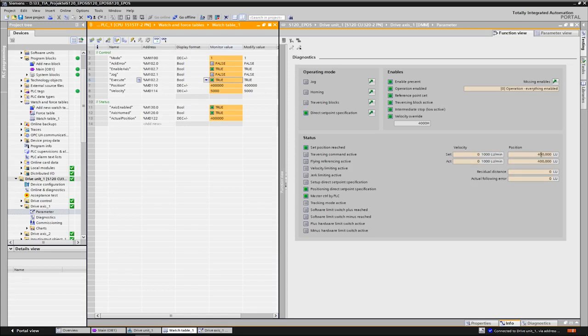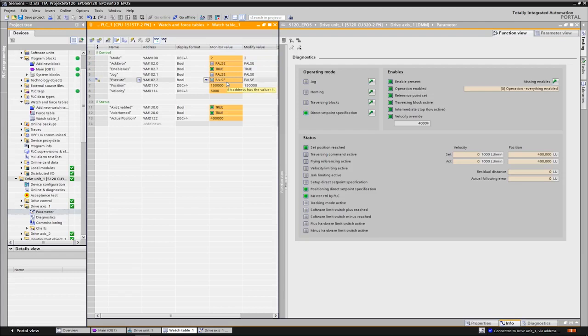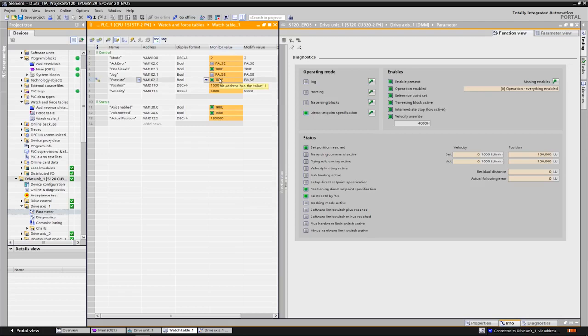We proceed with absolute positioning in the same way. We choose mode 2 and set the setpoint position to 150,000 LU, which stands for 150 millimeters. We start again with execute and we can see that the axis now moves absolutely to the specified position. The manual contains a detailed description of the additional modes such as jogging or referencing.